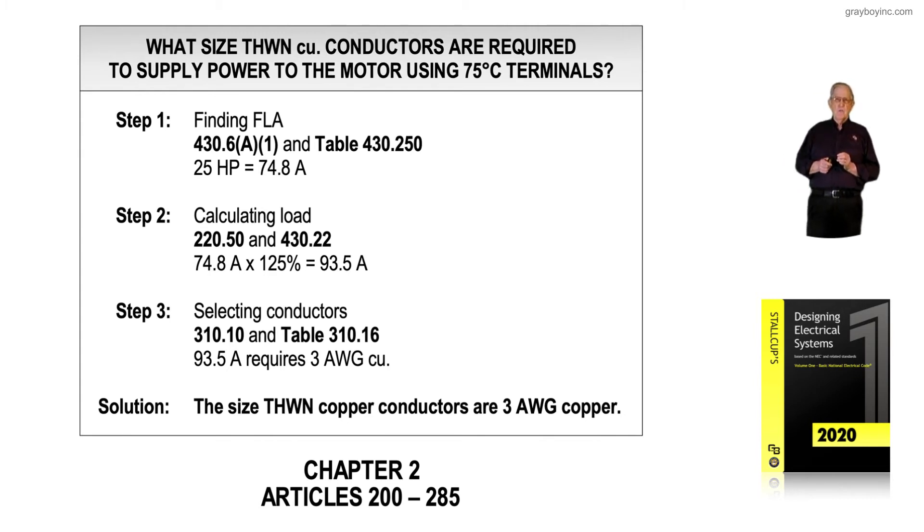Step three refers us to the sections that size these conductors. We review 310.10 / 310.10 Informational Note 2 — in the 2020 edition, 310.10 Informational Note 2 states that THWN conductors at 75-degree terminals can be used in dry or damp locations. We then select from Table 310.16 (previously 310.15B16 in the 2017 edition). The solution is number 3 AWG THWN copper conductors.